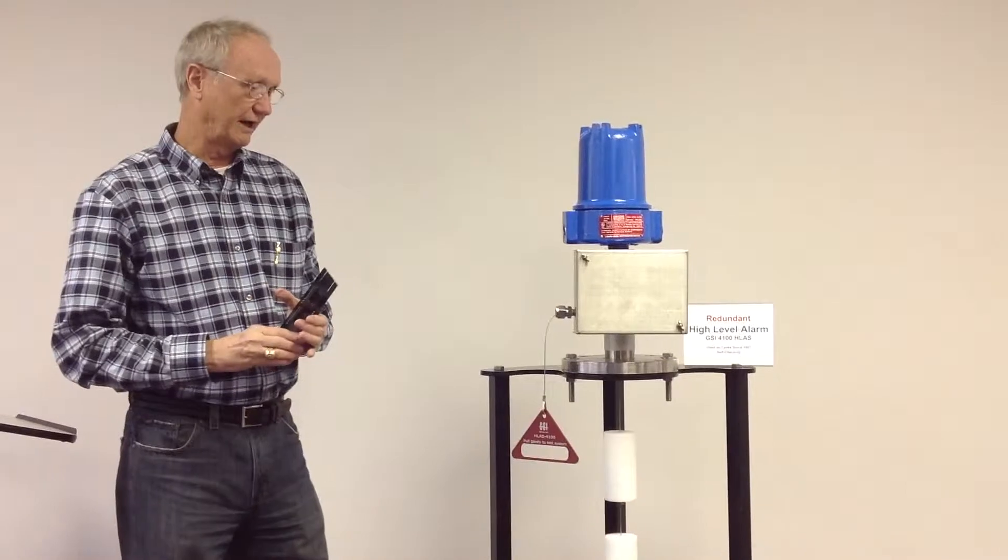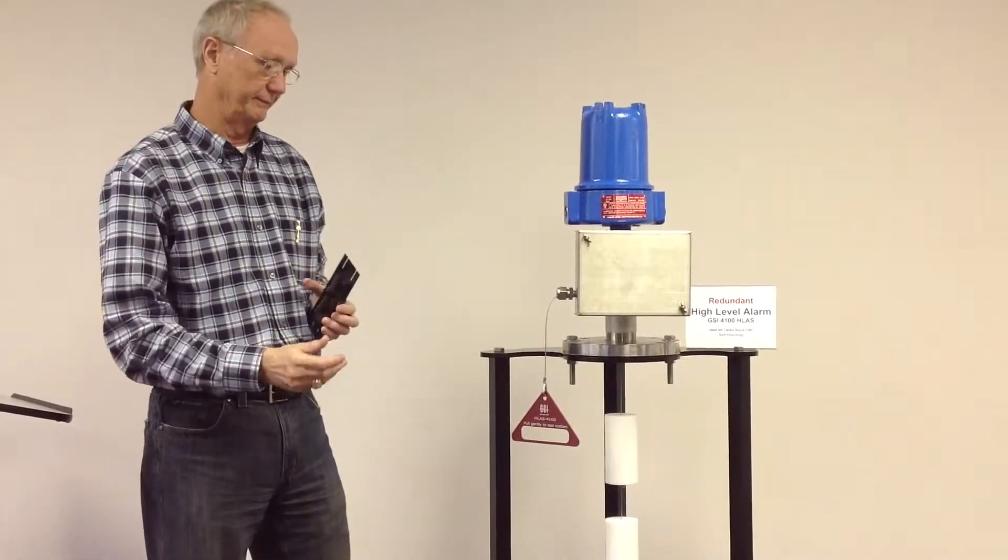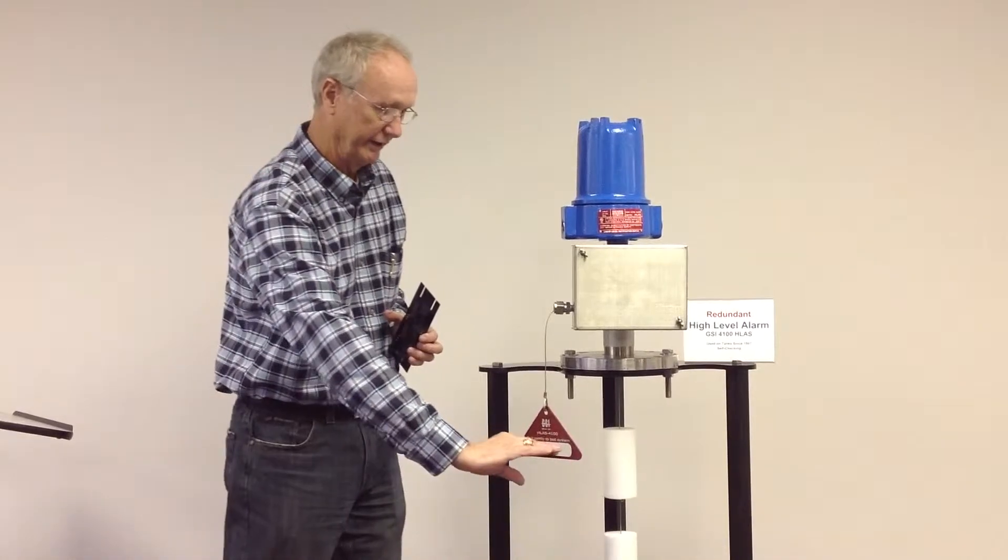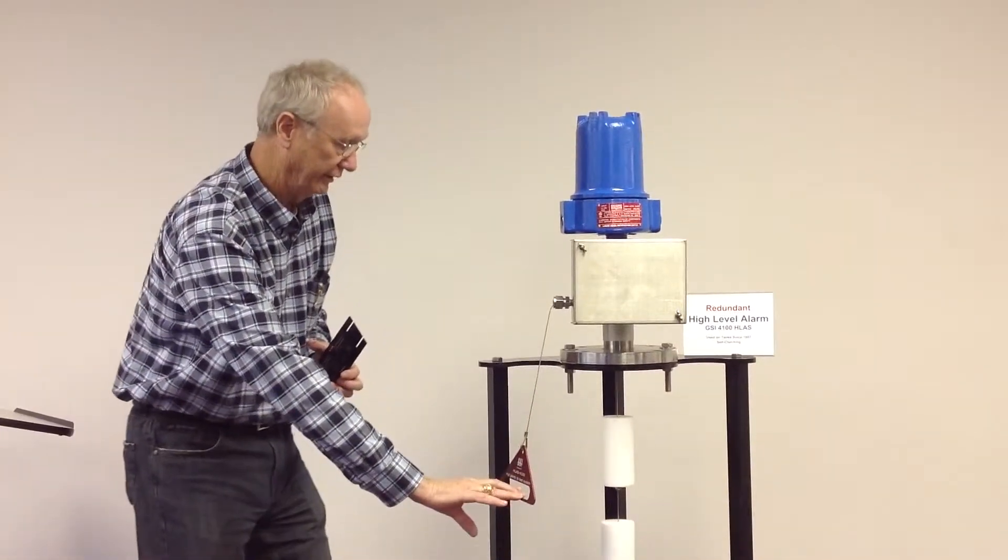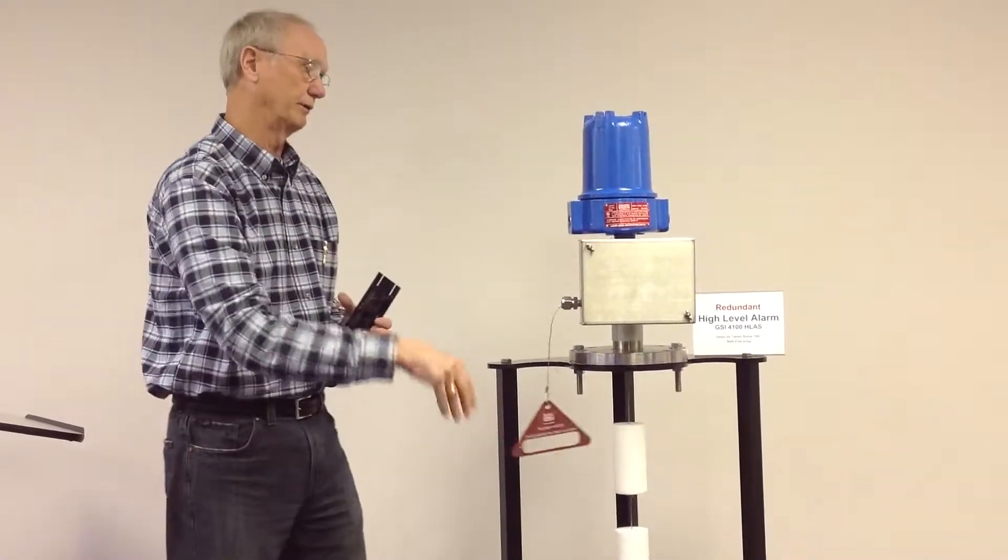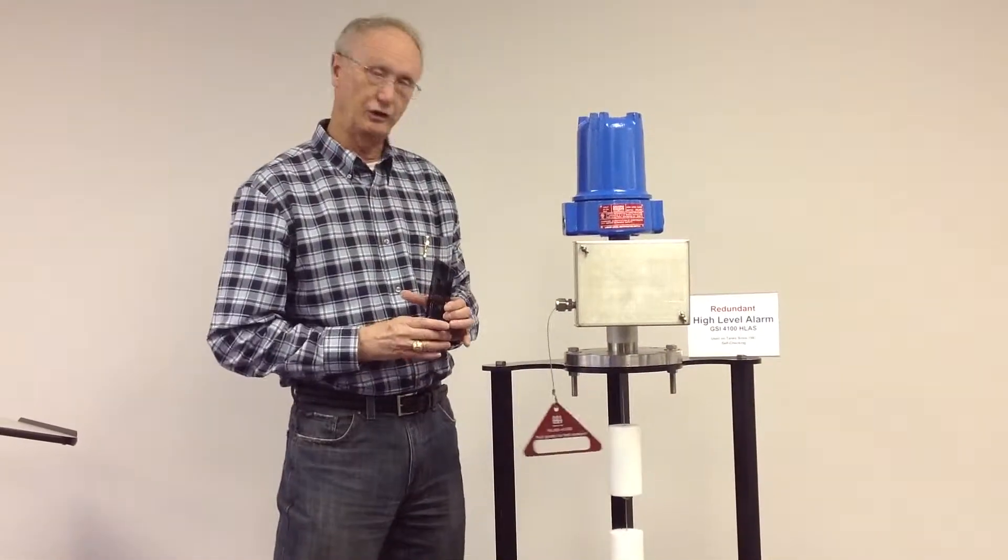This unit has an operational checker located at ground level. At any time, an operator can go out and pull the handle. It will lift both displacers and check all the components within the switch, including the spring.